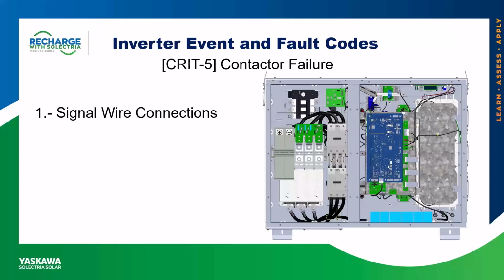If it doesn't go away, then the next step is to check continuity on the contactor tab. Now, important, this has to be done with the unit completely de-energized. And what we mean by that is the technician's going to have to go to the AC panel and turn off the breaker that feeds AC voltage to the inverter. Likewise, they will have to go to the DC combiner box, turn off the combiner so there's absolutely no AC or DC voltage going to the inverter.